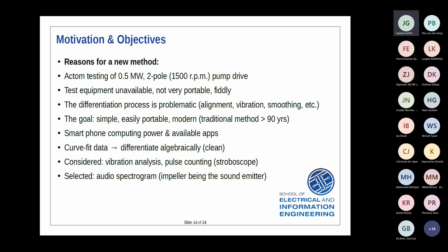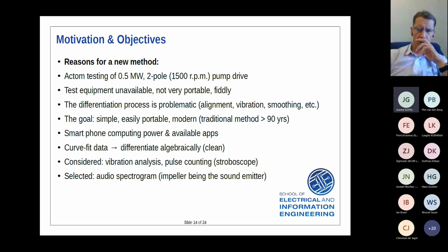Okay, so the equipment that we needed so far, we had to have a handheld tacho generator, some op-amp differentiator circuit, the power supply for that, all the cabling, and then our storage oscilloscope. The equipment becomes quite unportable, and it actually needed several people to help you. One to do the voltage measurement, one to hold the tacho, one to do the readings on the scope, and another one just to manage the whole thing. And it becomes quite fiddly, especially with the tacho generator being held against the shaft, and particularly on the large machines. Not only is that shaft spinning at a very intimidating 1500 RPM on this machine, but also it's floating backwards and forwards through the bearing. So it's actually quite a task to do it.